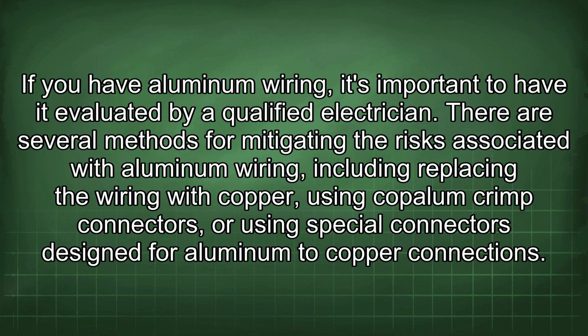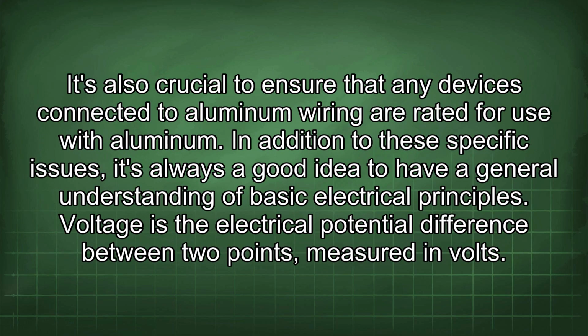There are several methods for mitigating the risks associated with aluminum wiring, including replacing the wiring with copper, using copalum crimp connectors, or using special connectors designed for aluminum to copper connections. It's also crucial to ensure that any devices connected to aluminum wiring are rated for use with aluminum.